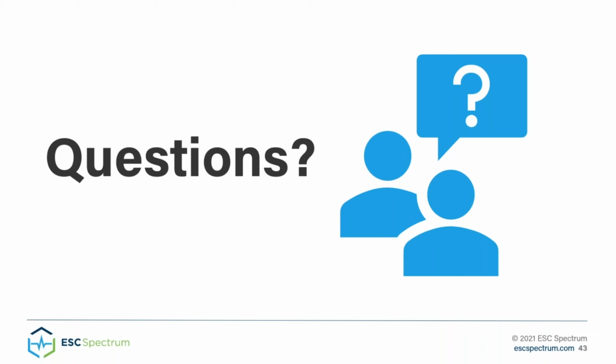And then will you get an alarm or email for each individual minute, or will only one run until the alarm is cleared? You'll get a StackVision alarm for each time that it has happened. And the email will not come in for each time it happens, because as long as you have the aggregate email option selected in the alarm notifications table, as long as that's set to true, then all of those 1 minute alarms will be consolidated into one email to show you how long it happens.